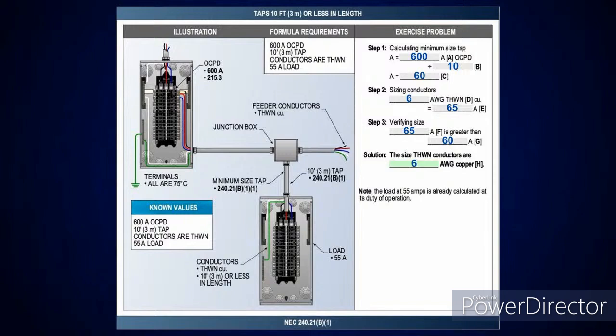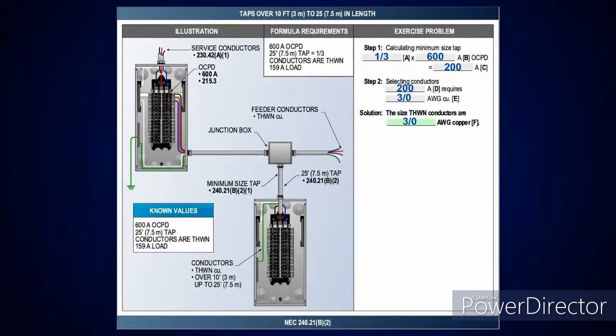But here in the illustration, I've got a 600 amp overcurrent device upstream. I'm going to make a tap off of that feeder circuit that's going out. So I'm going to divide that by 10. That'll give me 60 amps. I go over, look at table 310.16. We're using the 75 C terminals. Come down the next size above at 65 amps, which is going to require a number 6 conductor. So therefore, we verified that the 65 amps is greater than the 60 amps. Therefore, the size THWN copper conductors are number 6. Very simple.